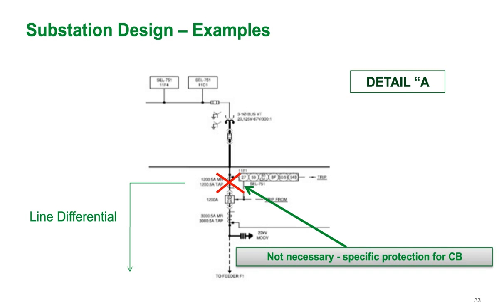Is this gear close coupled available? So typically gas insulated gear is not close coupled like with a transformer or a motor control center. The reason is that most GIS switchgear uses a very special bus bar configuration, whether it's all sealed in gas or even if it has a solid insulated and shielded insulation. It's a very unique bus bar configuration. So typically what we'll do is we'll cable down the bottom. Most if not all GIS switchgears are bottom entry. You can cable down and then into an adjacent transformer or a motor control center or something like that.